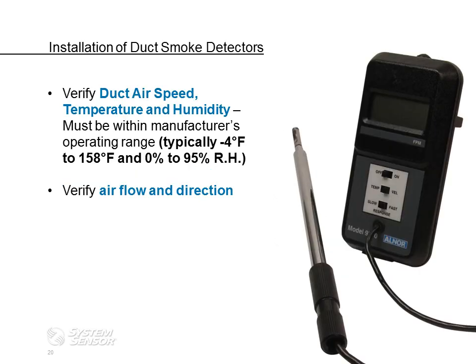One of the most important things and one of the first steps that we do in installing a duct smoke detector is we need to verify the duct airspeed, temperature, and humidity. And all of those must be within the manufacturer's operating range. Typically for temperature, -4 to 158, and humidity at 0 to 95%. We have to make sure that we have the proper airspeed, temperature, and humidity for that detector to function correctly. Again, we have to verify airflow and direction so that we know which way to orientate the sampling tube to ensure we have proper function.